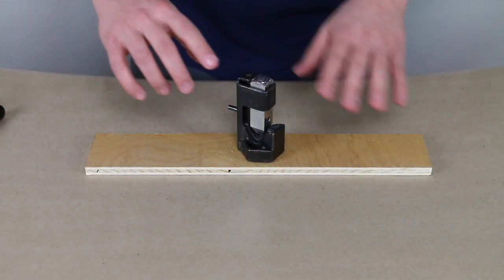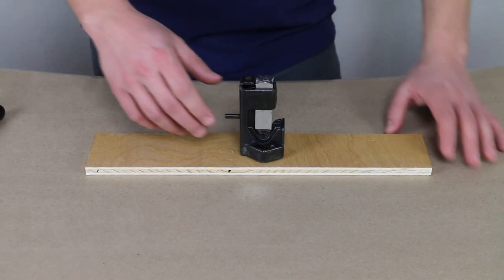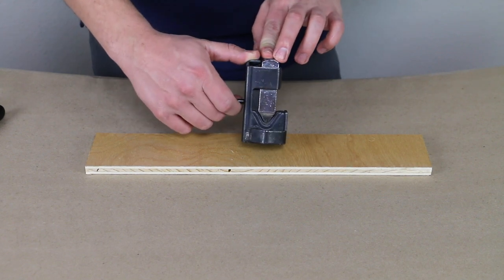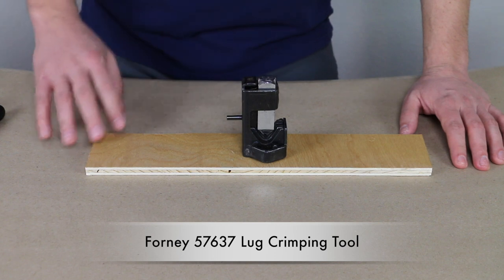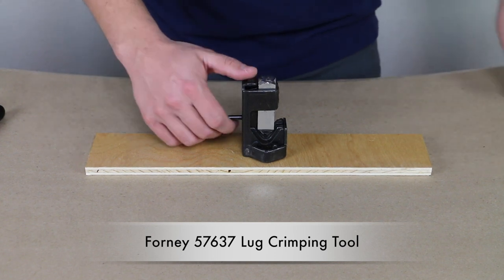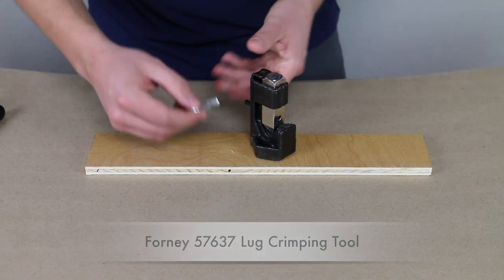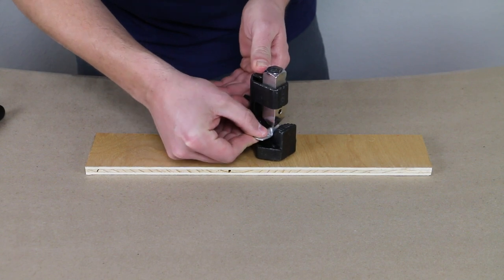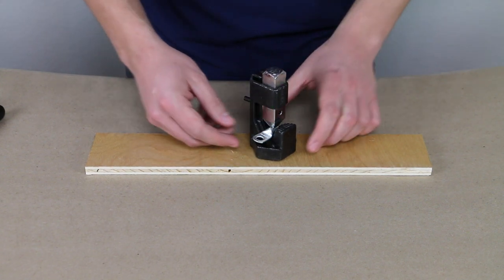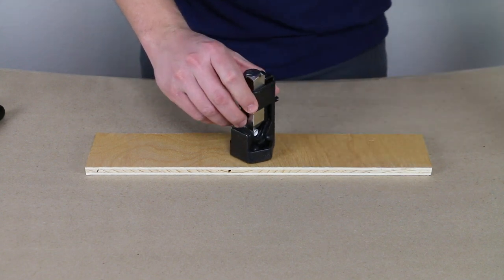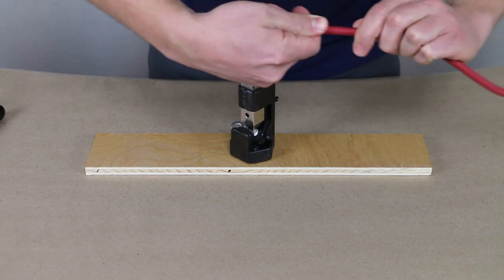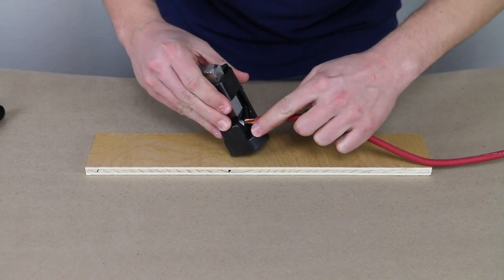All right. So we have the Forney lug crimping tool. This is from Forney. And I'll go ahead and put the model number at the bottom of the screen. This is about $20. So what you're going to do is you're going to retract the anvil and insert your lug terminal. So this is a six-gauge lug terminal. And you can see there at the back, you can insert your cable. So we've got a six-gauge cable and go ahead and thread that in there.